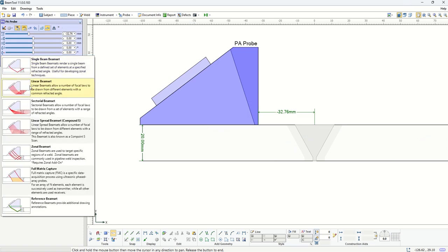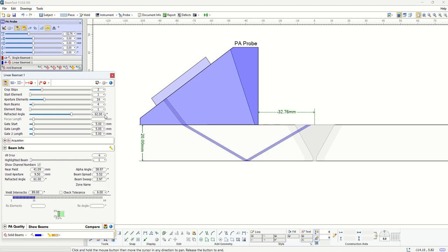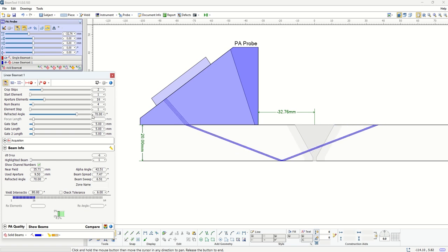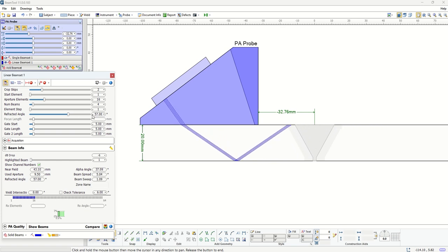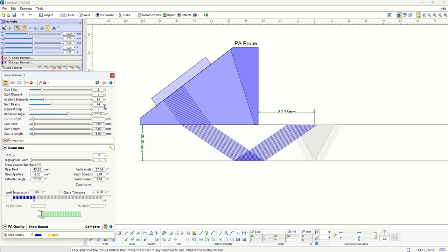The second option here would be a linear beam set. Linear beam set would be a series of beams that are all generated with the same angle. If we choose to change the angle, all of these beams will have the same angle. Other than a start element and aperture size, you also have the option on the number of beams.